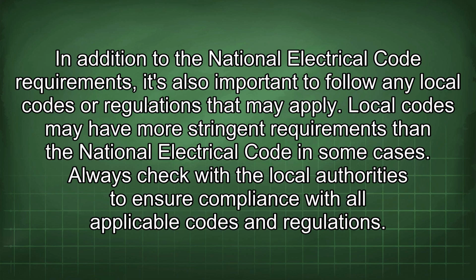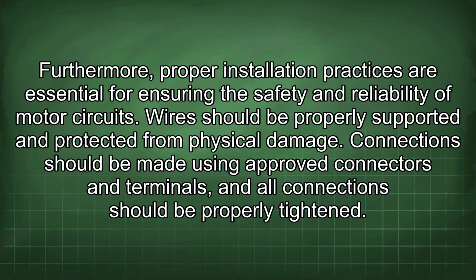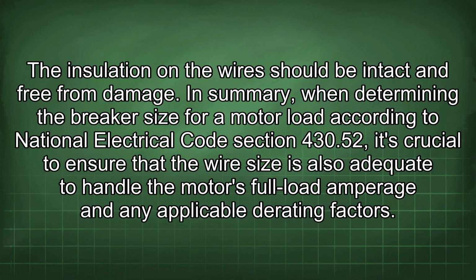In addition to the National Electrical Code requirements, it's also important to follow any local codes or regulations that may apply. Local codes may have more stringent requirements than the National Electrical Code in some cases. Always check with the local authorities to ensure compliance with all applicable codes and regulations. Furthermore, proper installation practices are essential for ensuring the safety and reliability of motor circuits. Wires should be properly supported and protected from physical damage. Connections should be made using approved connectors and terminals, and all connections should be properly tightened. The insulation on the wires should be intact and free from damage.